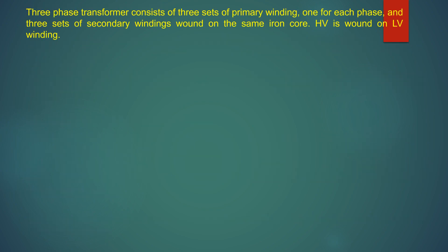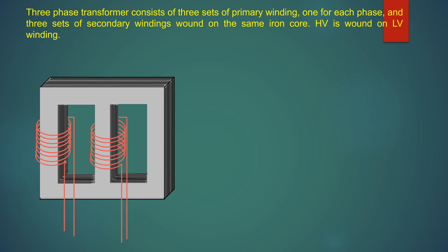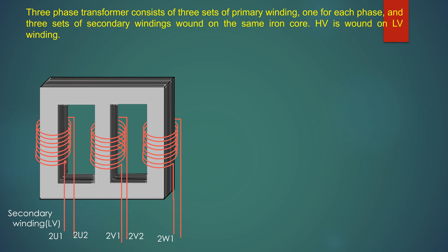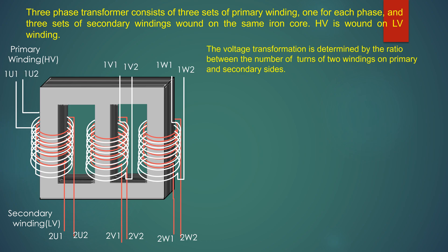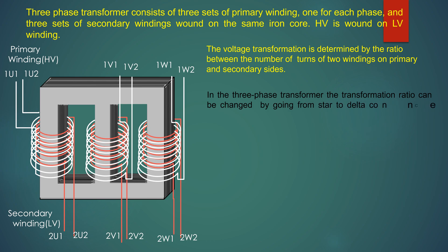A three-phase transformer consists of three sets of primary windings, one for each phase, and three sets of secondary windings wound on the same iron core. The HV winding is wound over the LV winding. The voltage transformation is determined by the ratio between the number of turns of the two windings on the primary and secondary sides. The transformation ratio can be changed by going from star to delta connection, giving mixed connections where the ratio between the main voltages is not equal to the turns ratio.